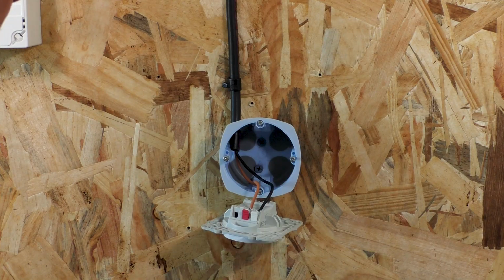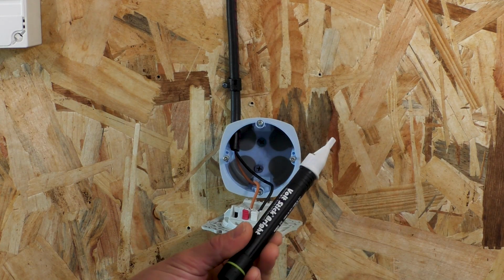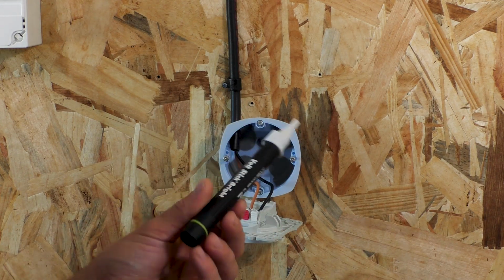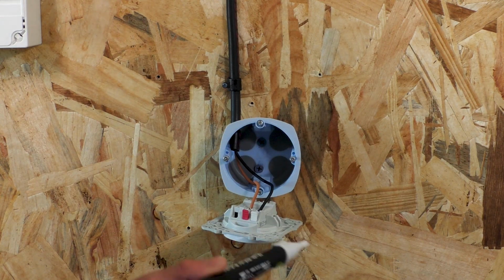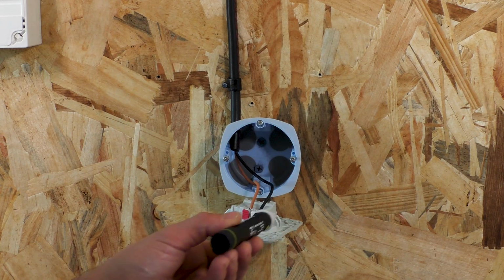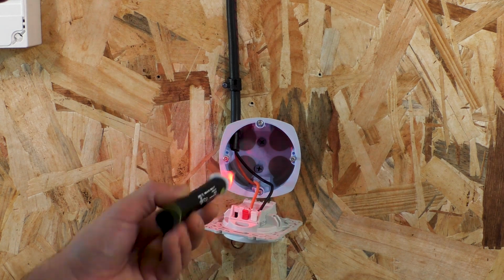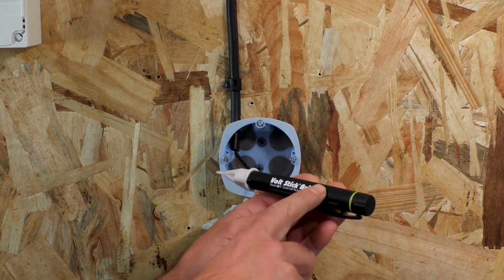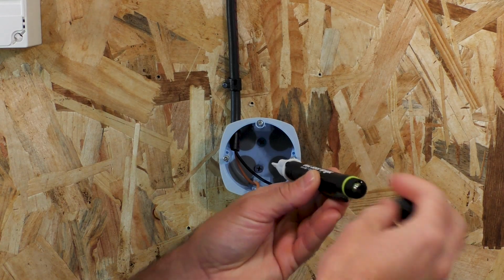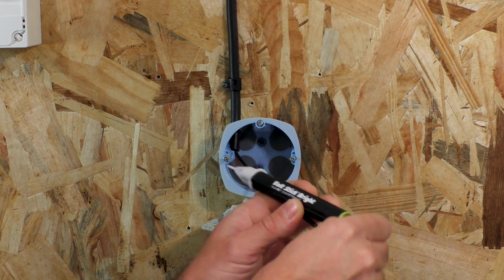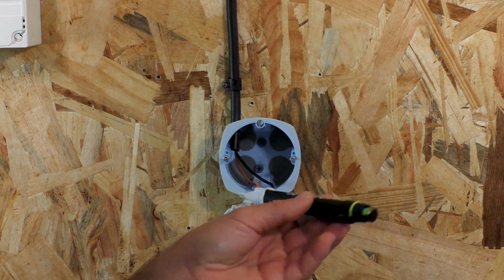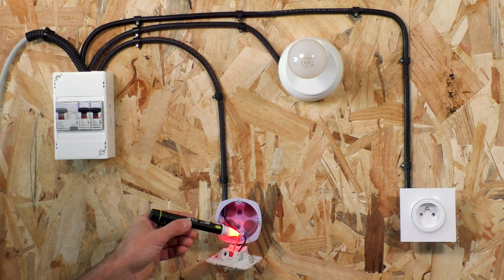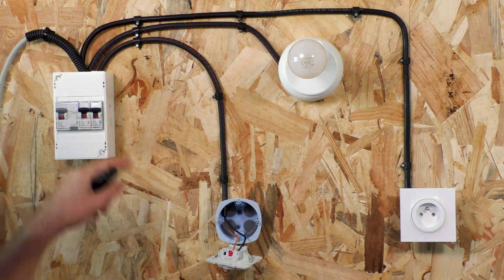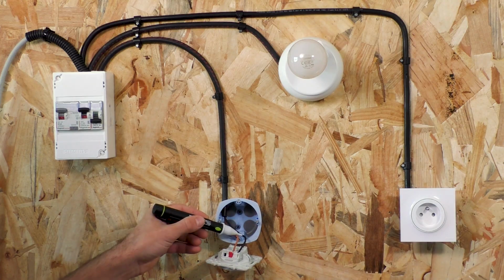One important note: these testers can give you false readings in both directions. A false positive when it detects voltage that isn't actually there, often if you move it too quickly over a wire or if the non-energized wire is near the live one. And a false negative if your batteries are empty or there is a bad connection at the tester. It won't beep even if the wire is live. So always test it first on something you know is energized to make sure your tester works. Then turn the breaker off and test again.